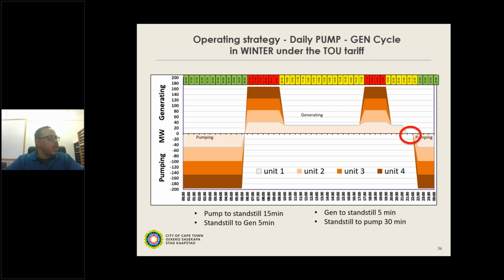So if we start on the left-hand side at 0030, that is when we typically have 3 or 4 units running in winter or high peak demand, which corresponds to running from 12:30 at night to early hours of the morning till about 5 or 6 o'clock in pump mode. So we're busy pumping from the lower dam to the upper dam. Then in the morning we will shut down after about 6, and swing the units over for the morning peak to gen.